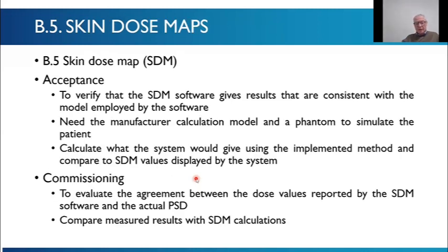The skin dose map. Yeah, I'll give a quick summary of this. This is still a bit, I wouldn't say work in progress, but a lot of systems have this skin dose mapping where a model is programmed into the system. The system measures the geometry, the distances, the field of view, the factors, and it predicts what the peak skin dose will be on a model of the patient. We want to verify this model. So the first step is you need a manufacturer calculation model from them. So you need to communicate quite closely with the manufacturer and ask for their calculation model. You set some views and projections, measure the X-ray factors, put those into the model offline, and then see that the system is displaying the things that you've calculated with the offline method. I think that's how that works. Someone will correct me on that if that's wrong.